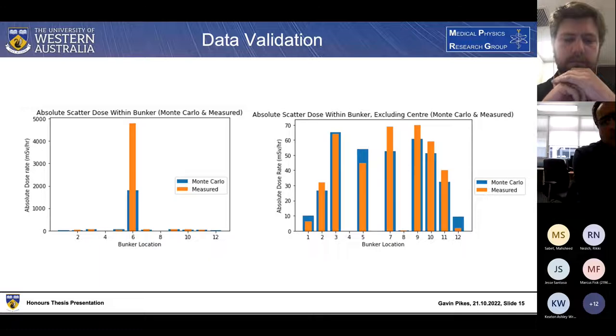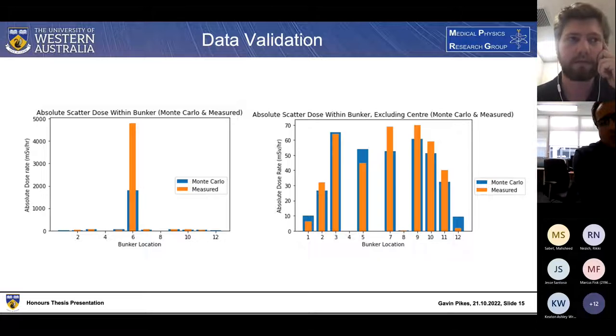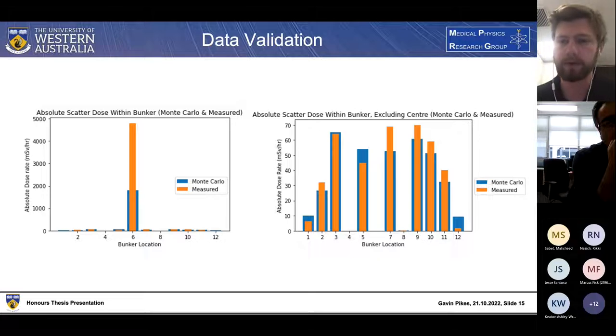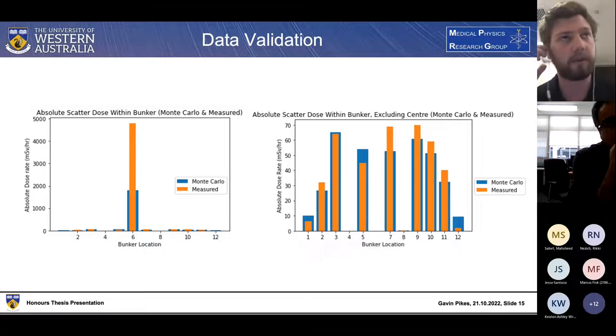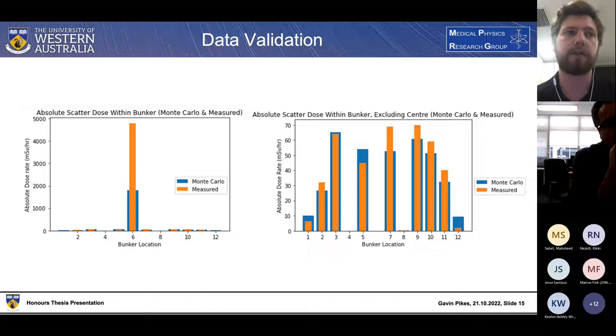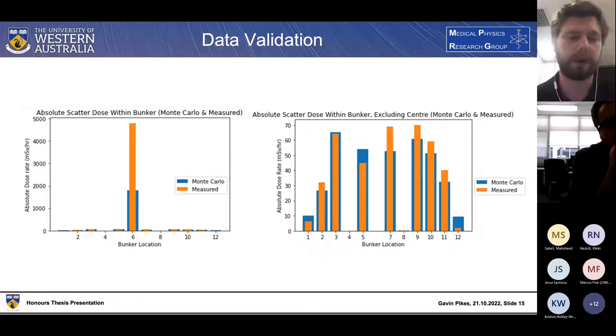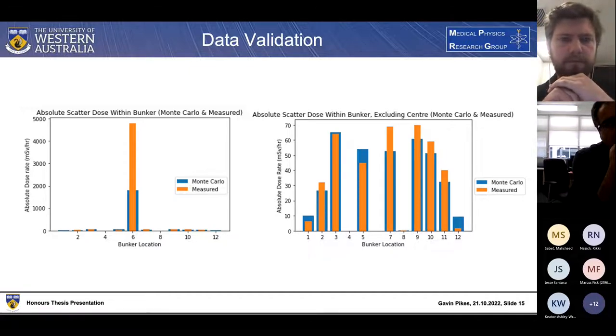A follow-up question asks whether the maze entrance dose rate calculations used a fixed beam direction or sampled from multiple directions. The measured results used the beam going directly downward. The simulated measurements of dose at the maze entrance used the beam at 0, 90, 180, and 270 degree positions, simulating the proper use factor of 0.25 for each of the four directions.